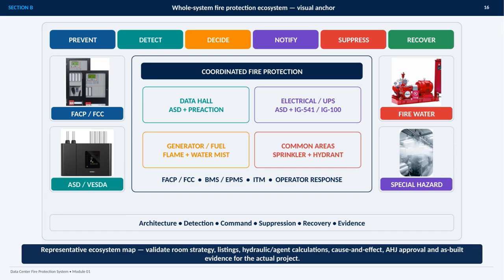At the center, the coordinated fire protection model links the data hall, electrical and UPS spaces, generators and fuel areas, and common areas. Each environment has a representative strategy: ASD with preaction for the data hall, ASD with IG 541 or IG 100 for electrical and UPS spaces, flame detection with water mist for generator and fuel areas, and sprinkler with hydrant protection in common areas.